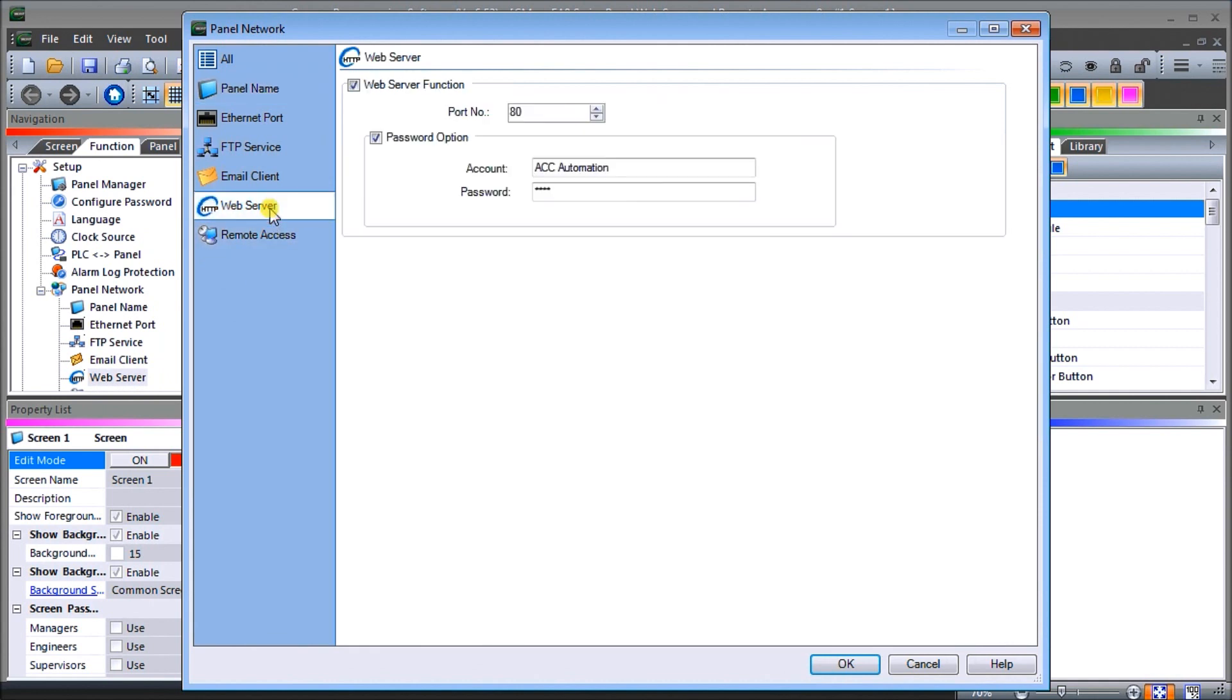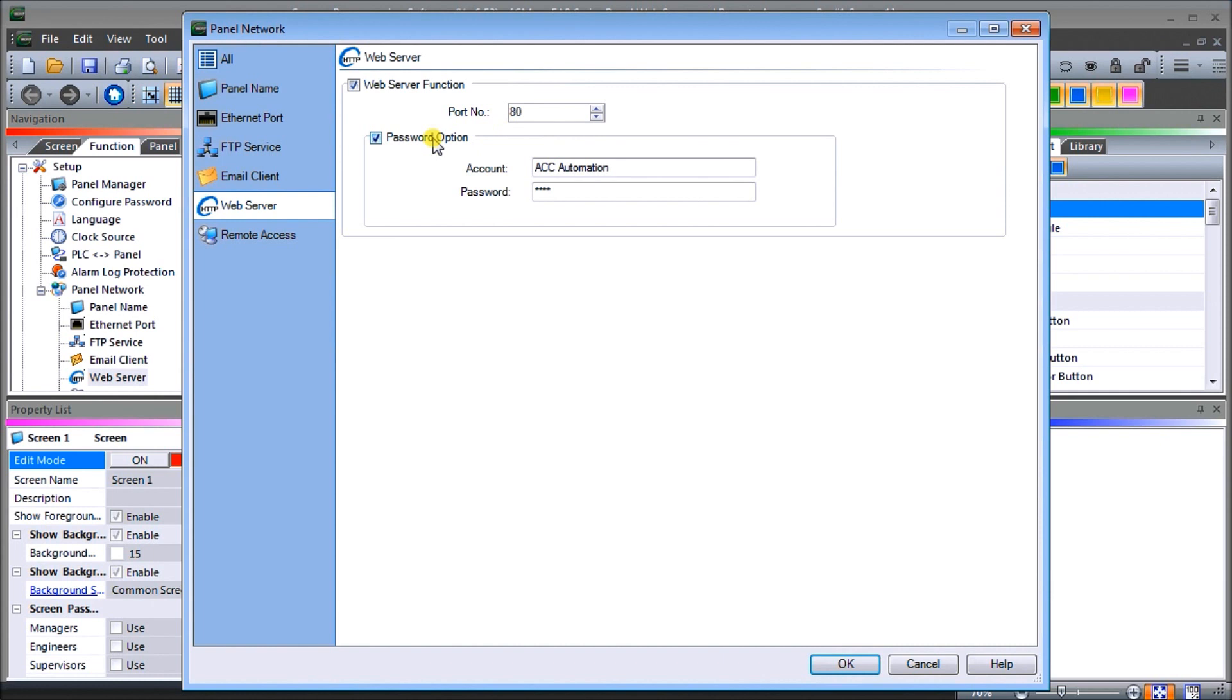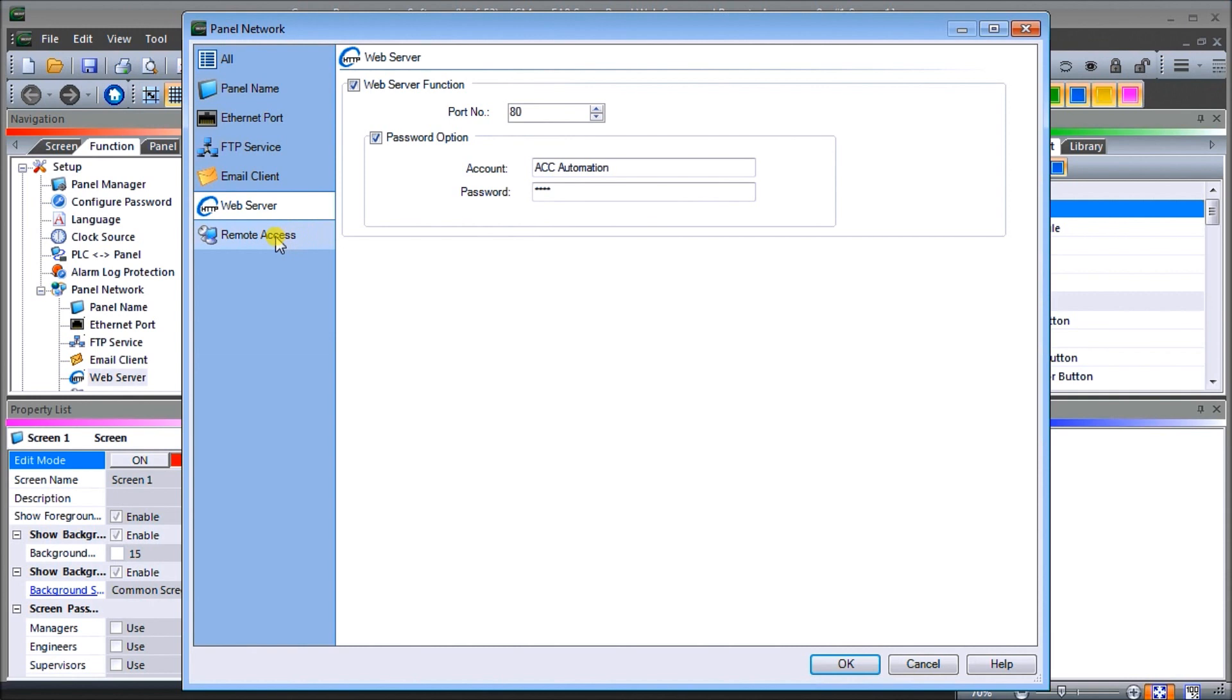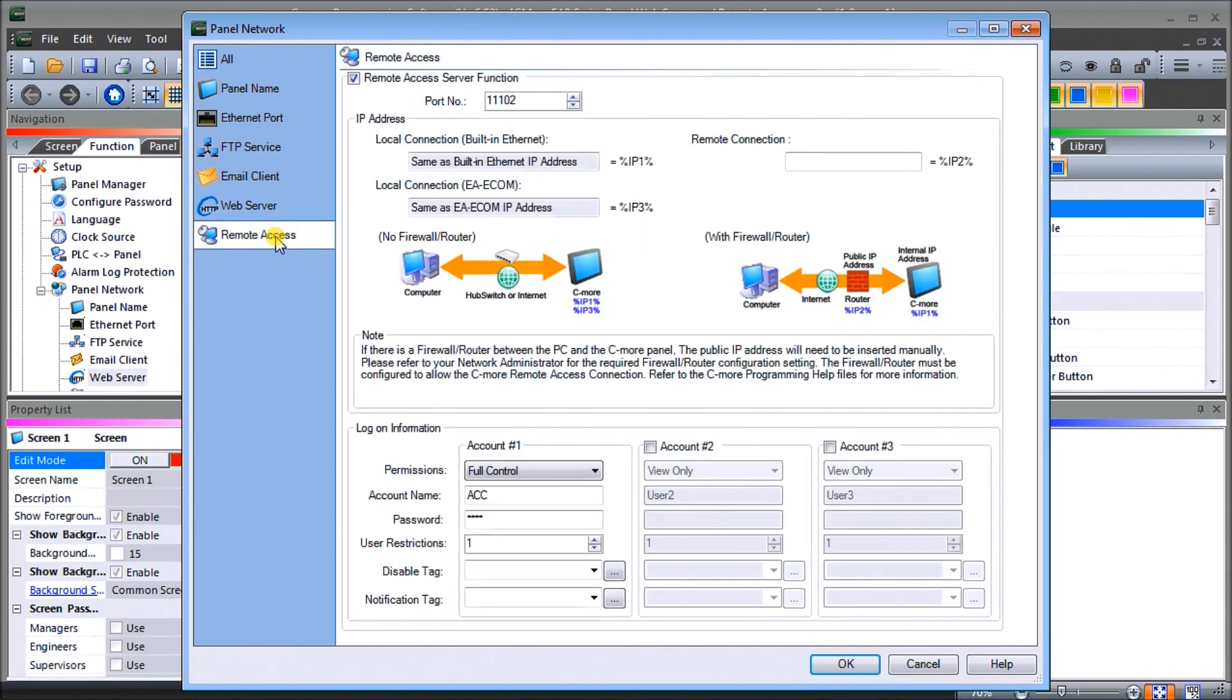We'll go to our Web Server. Under web server we enable our web server function, which is right here. We click that on and we put port number 80, which is the default port for web server. Then we have our password option. Our account will be ACC Automation and our password we're going to put acca, all small case. We'll also look at our remote access as well.